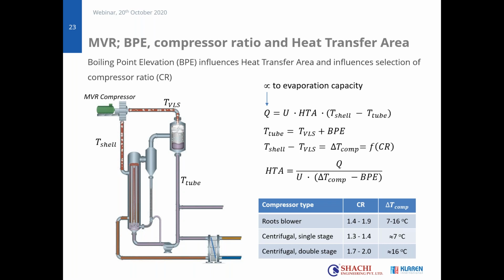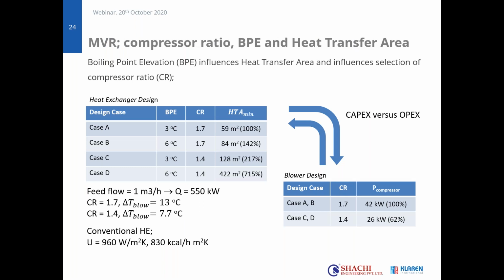But with a double stage, you could go to higher compressor ratios, and of course you have more driving force for the heat exchanger. And that's what I show you in the next slide, is how this affects the design of your heat exchanger. So in this slide, you see some data for a typical case, and I've calculated based on a conventional heat exchanger.